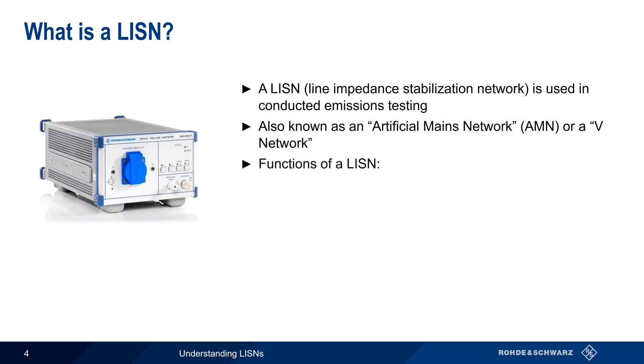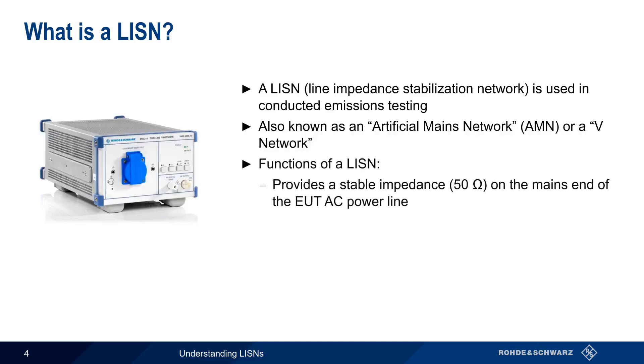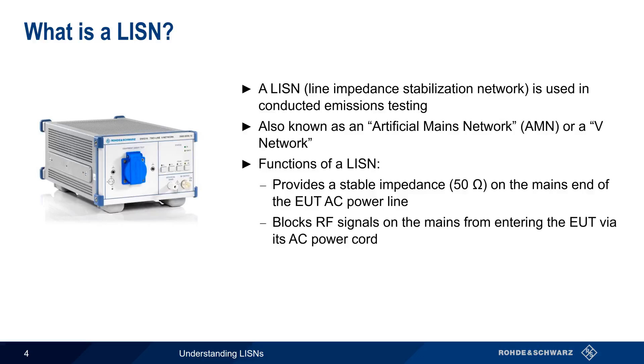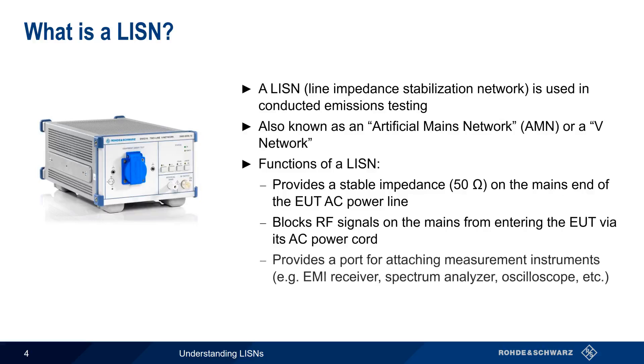A LISN has three main functions. First, it provides a stable impedance, usually 50 ohms, on the mains end of the EUT's power cord. Another important function is that it prevents RF signals on the AC power or mains network from entering the EUT via its power cord. And lastly, a LISN provides a port for attaching measurement instruments, such as an EMI receiver, spectrum analyzer, or oscilloscope. In the remainder of this presentation, we'll explain these different functions and how they're used in EMC conducted emissions measurements.